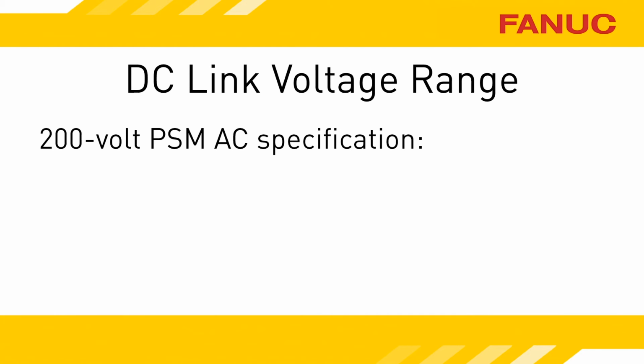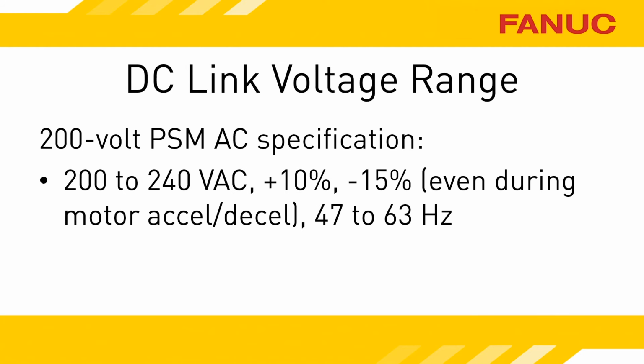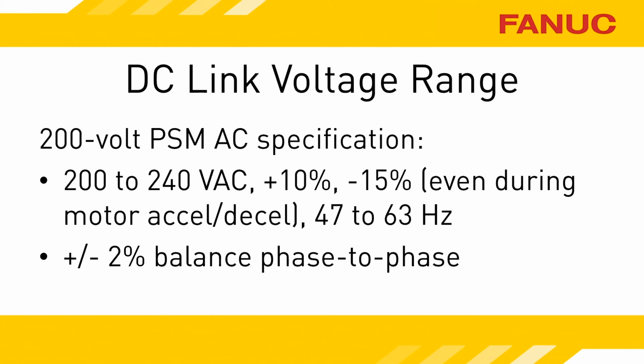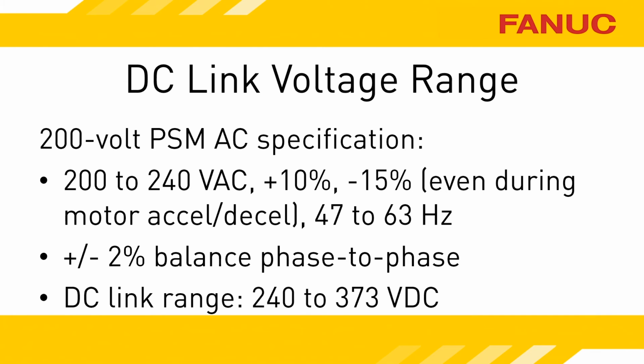For 200 volt drives, the AC specification is 200 to 240 volts AC, no less than 170 volts, no more than 264 volts. This includes highly kinetic energy events like accelerating and decelerating motors, and lightning strikes in the area. Phases need to be within 2% of each other, so we're talking very balanced power. Based on the incoming power, your DC link voltage could be anywhere from 240 to 373 volts. Since we're talking about DC link undervoltage, we're most concerned with a DC link that's under 240 volts.